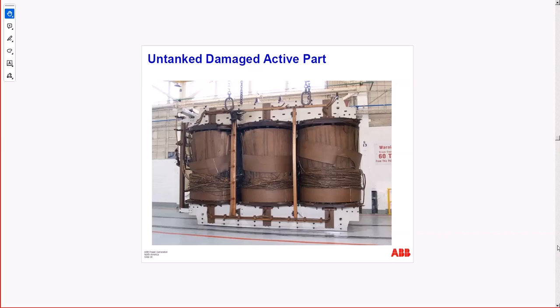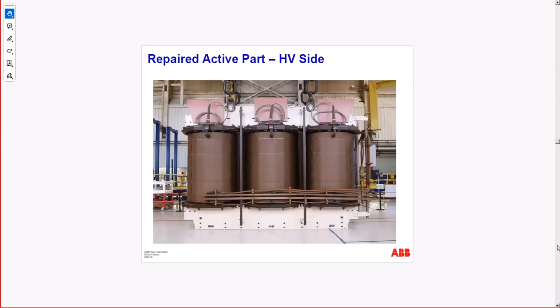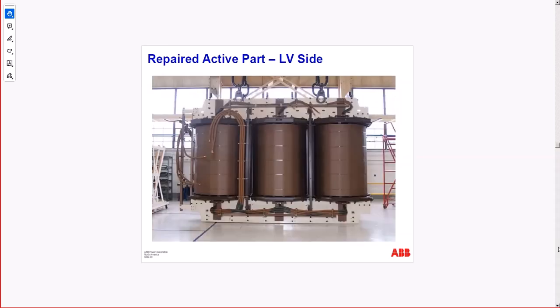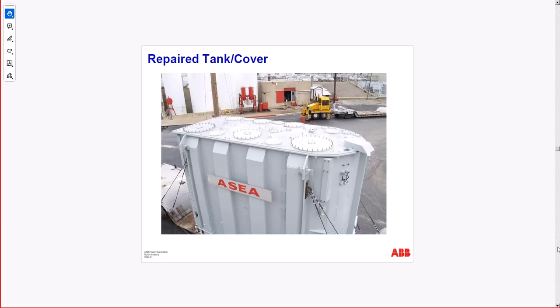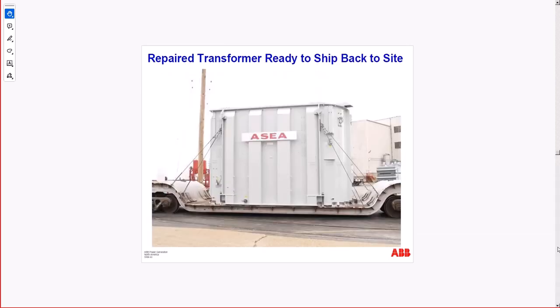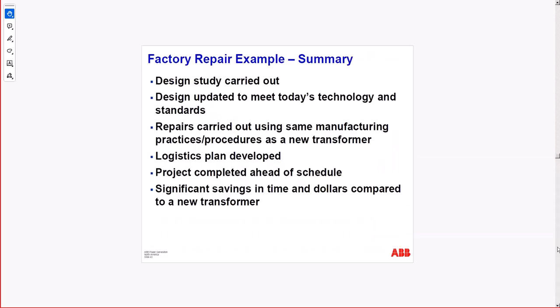Tank damage, active part with collapse of the windings. You see here repair of the same core. So if the core is okay and you don't have a short circuit between the different laminated core sheets, those are 0.35 millimeter to decrease the actual losses, eddy currents and hysteresis. So you should have insulation in place between them. They also deteriorate from movements and active short circuit or too many connections of the power. Repair active part, low voltage side, and tank repair. So this is a success story, back to site after the damage that you saw happened.